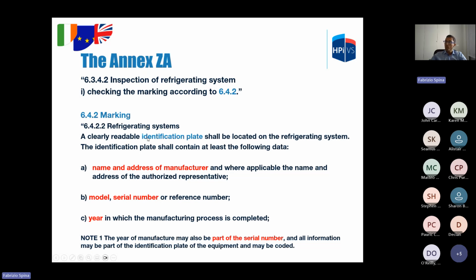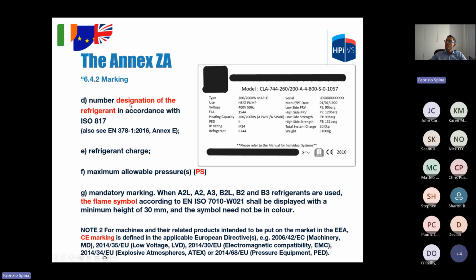The point 6.4.2 specifies what must be displayed on the identification plate, and that is the name and address of the manufacturer, model and serial number, year of manufacturing. The year can also be part of the serial number, so there's no need to specify only the year if your model number includes also the year of manufacturing. The designation of the refrigerant, charge, the maximum allowable pressure, and I can say also temperature. The flame symbol when flammable refrigerants are used, and the CE marking when applicable directives are applied and satisfied.